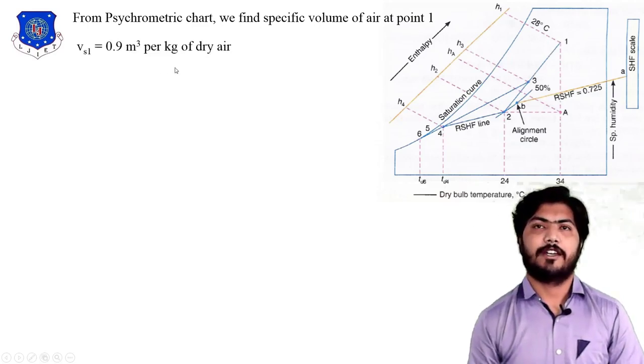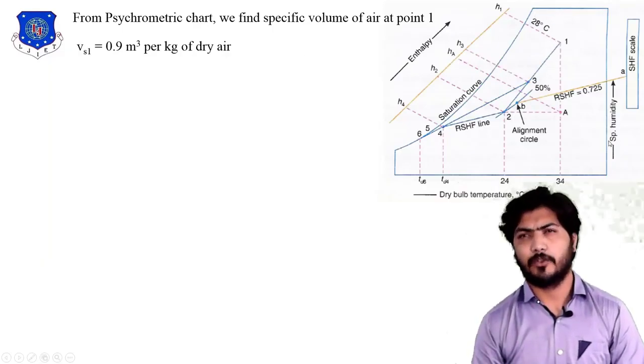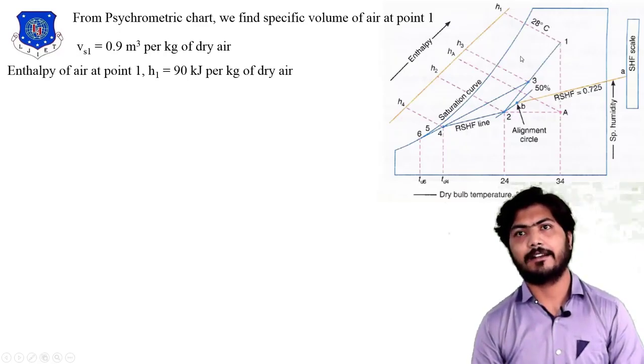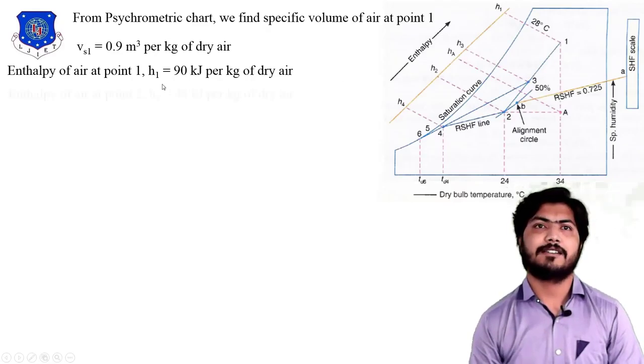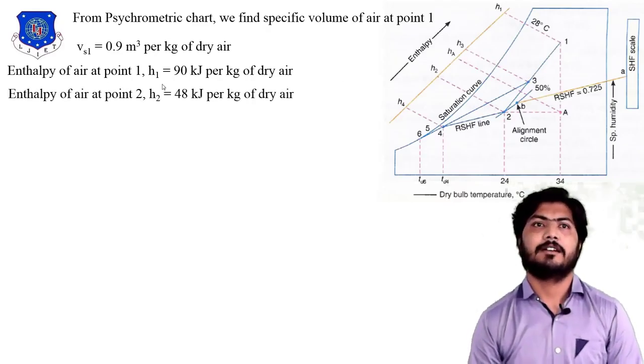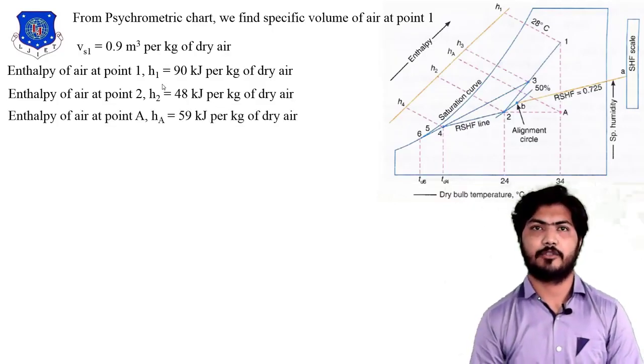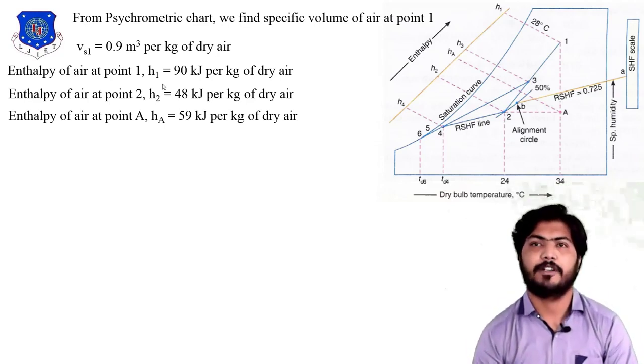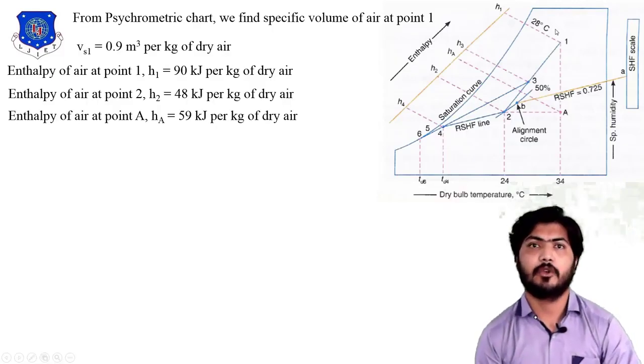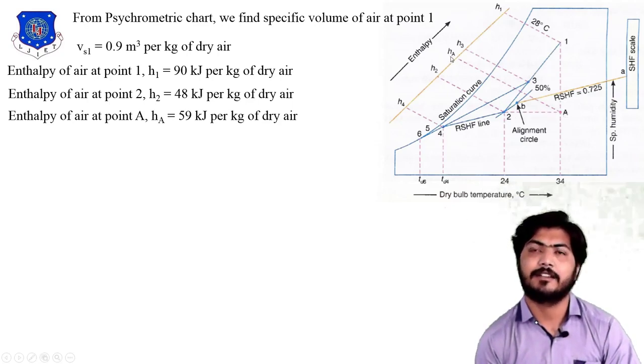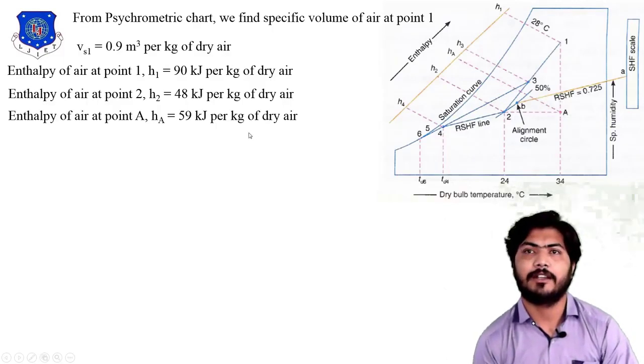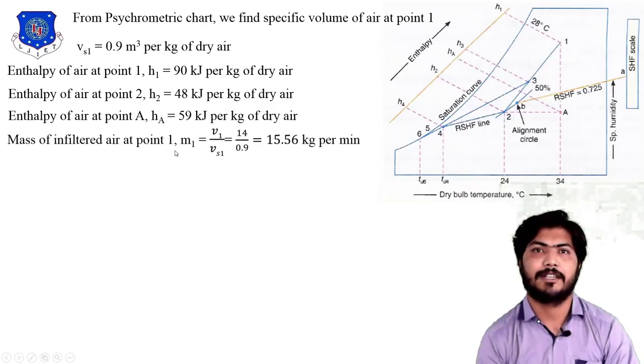From the psychrometric chart, the specific volume at point 1 is 0.9 cubic meters per kg of dry air. For point 1, we locate it on the psychrometric chart using the inclined specific volume line, giving 0.9 cubic meters per kg of dry air. The enthalpy at point 1 (H1) is 90 kJ/kg of dry air, enthalpy at point 2 (H2) is 48 kJ/kg of dry air, and the enthalpy at point A (HA) is 59 kJ/kg of dry air.